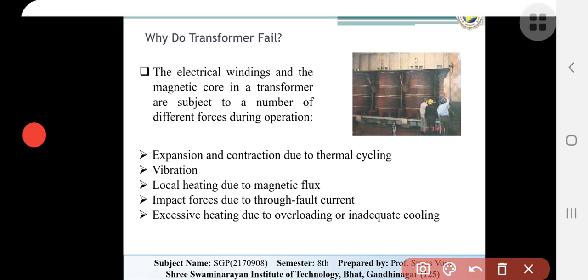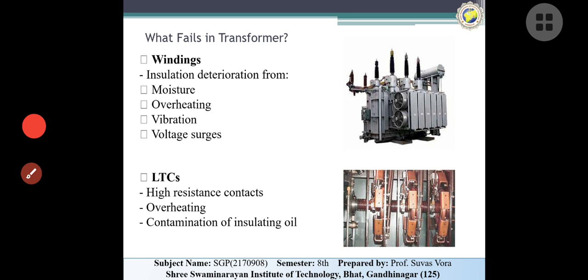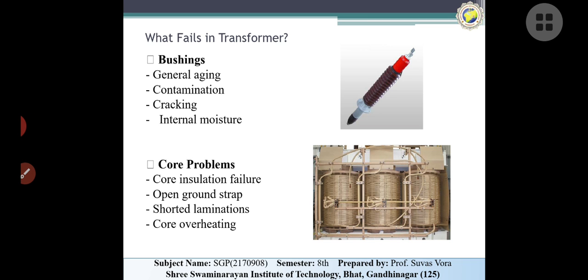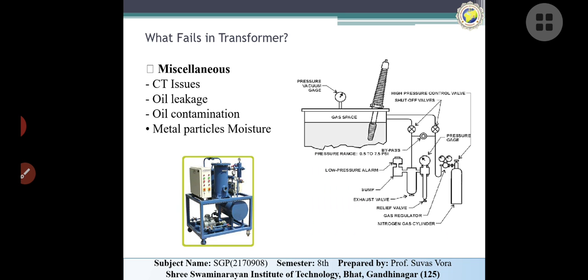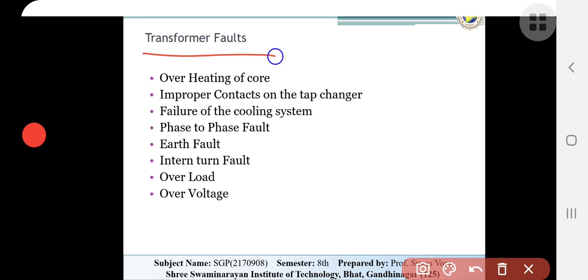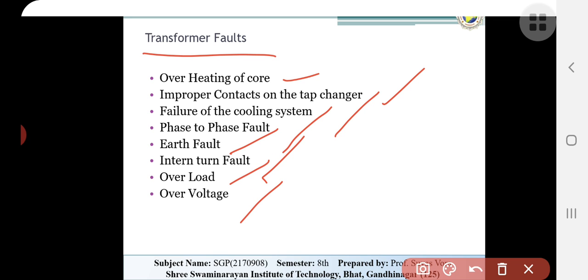Basically, we know from the previous lecture that there are a lot of forces on the winding during operation, so that is where most failures of transformers occur. Then the components with the most failures: the winding, then LTC, then bushing, core problems, then miscellaneous components. After that we studied transformer faults: overheating of the core, improper contacts, failure of cooling, phase to phase fault, earth fault, interturn faults, overload, and over voltage.